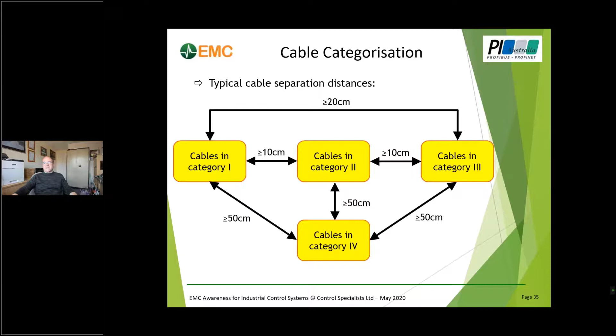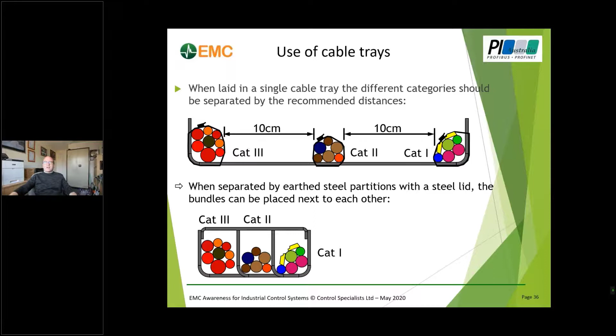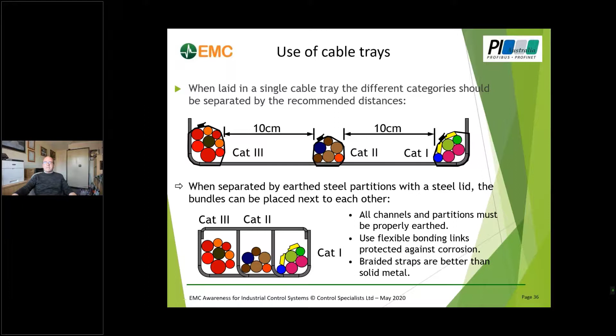If we've got these cables in different categories, then we might have this kind of thing. That's basically it. So if we were doing this in a cable tray, it would be something like this. And if space was short, then we might need to put it in a steel enclosure to achieve the same mitigation against coupling.